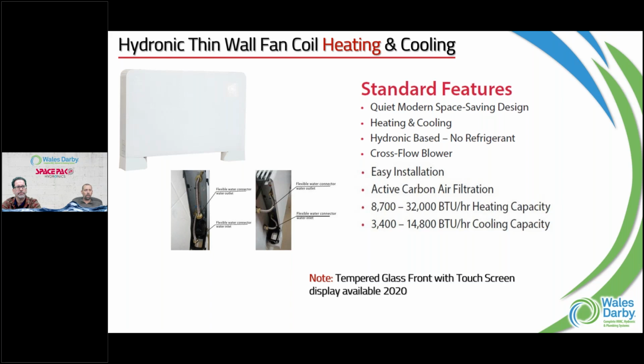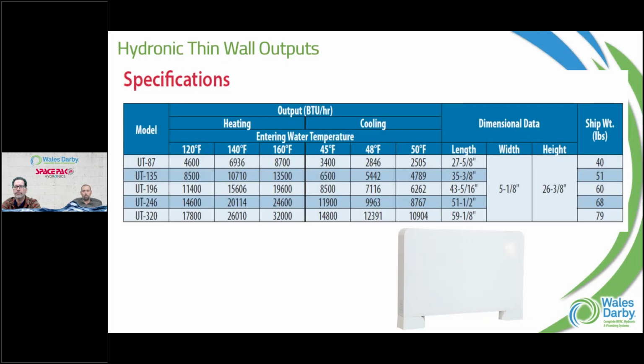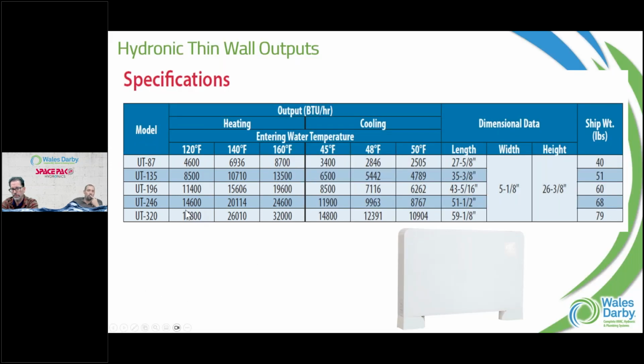So again, looking at the charts and understanding what my performance is going to be at 120 degrees entering water temp, I can get anywhere from 4,600 BTUs on the lowest model all the way up to just over 17,000 BTUs. That might be a big unit - it's almost 5 feet wide. But the BTUs I'm getting out of one thing on a wall - I don't have baseboard going all the way around.